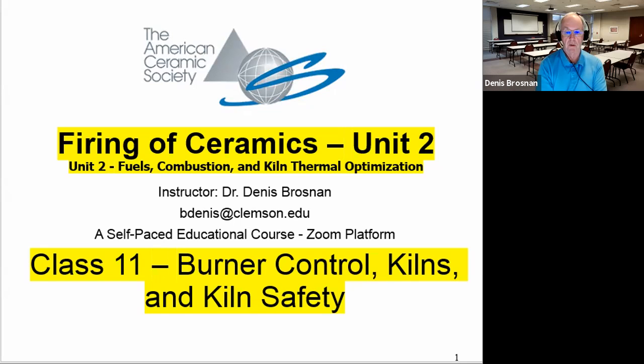It's very important. I've talked a bit about being able to look with your eyes and tell what's going on in terms of valve positions and things of this nature, observation ports on burners that you can look in and tell that the burners are operating, about flame supervision equipment that's automatic. So we've talked about a number of things. So we basically have the air or oxidant and fuel to the burners. Today we're going to talk about burner control and burner placement in kilns. We're still talking about gas and liquid fuels.